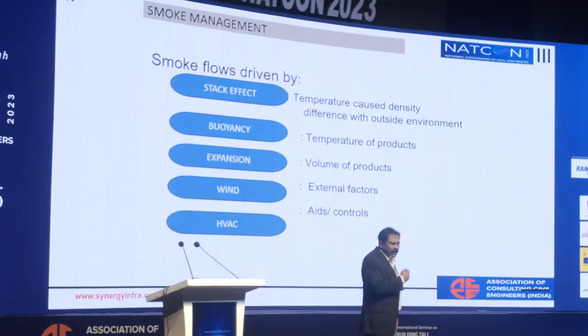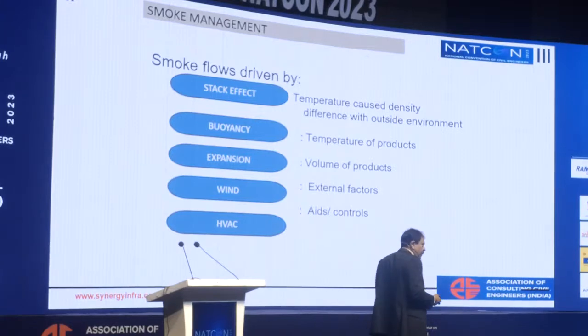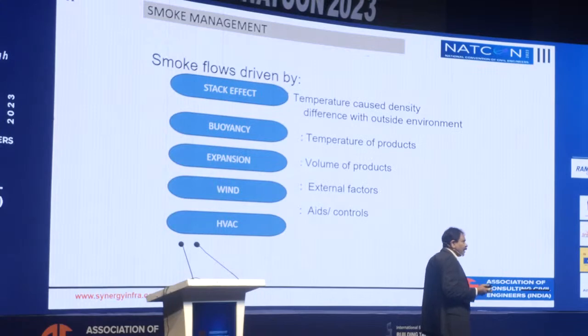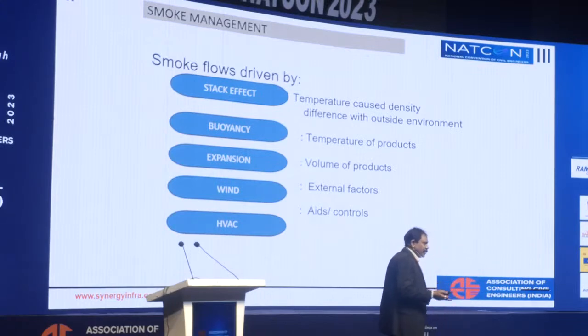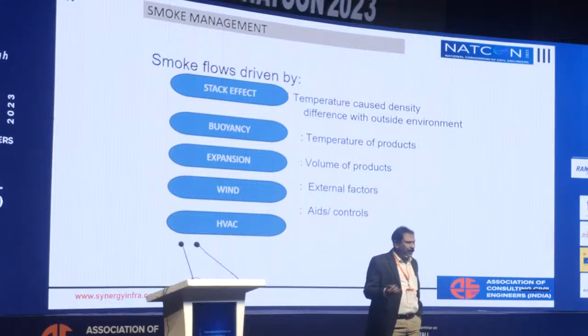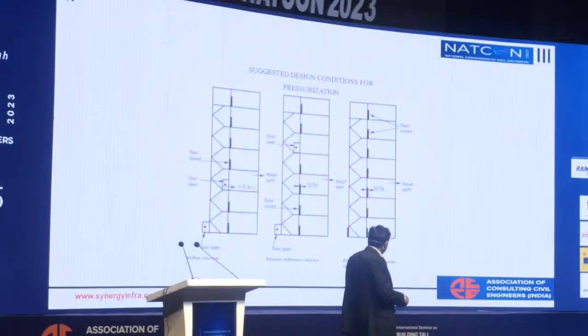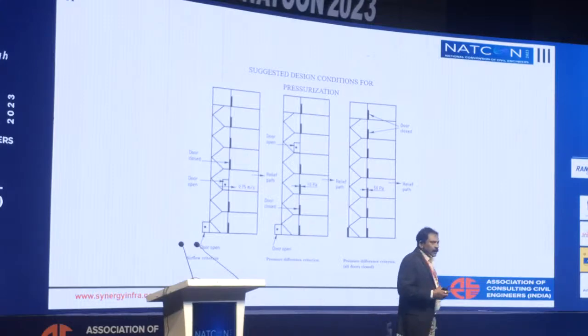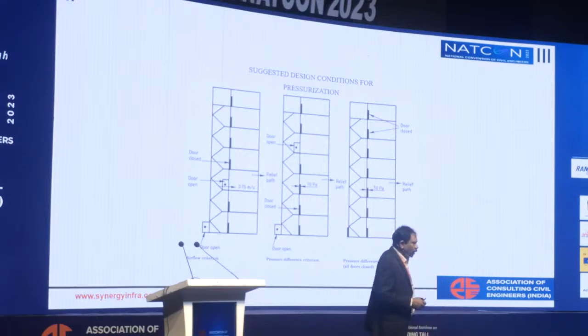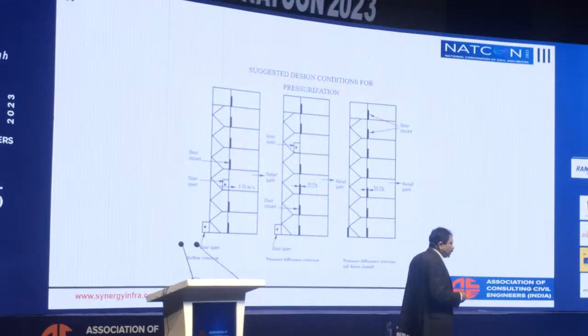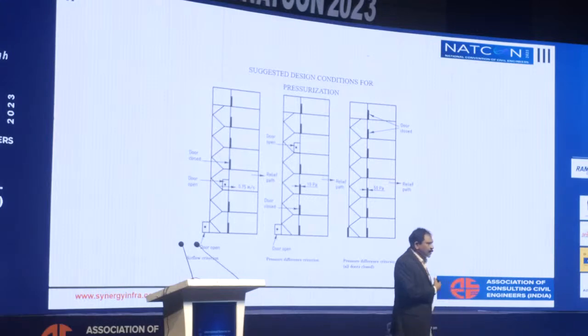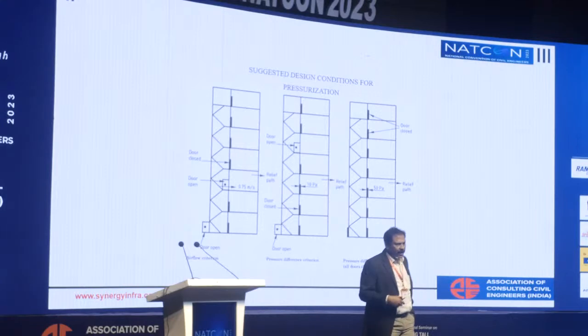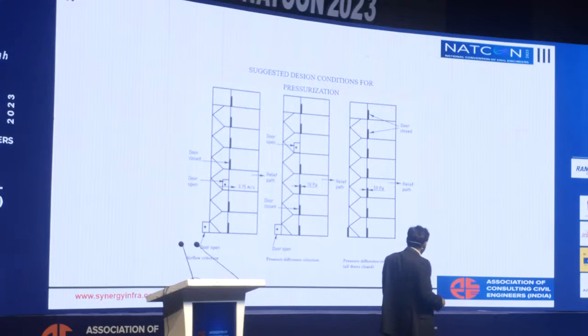One of the most important things when we talk about smoke management is the flow of smoke. This is due to stack effect, buoyancy, expansion of gases and wind direction, and also air conditioning ducting systems. They can aid or even suppress it, and can be used as dedicated or non-dedicated systems. Based on all these things, the safe routes have to be pressurized or protected. Our code allows natural ventilation for the staircases, irrespective of height. But as I was telling you, if you do an analysis using the stack effect and other things, we can't do with natural ventilation. We have to look at pressurization of these staircases and protect them.